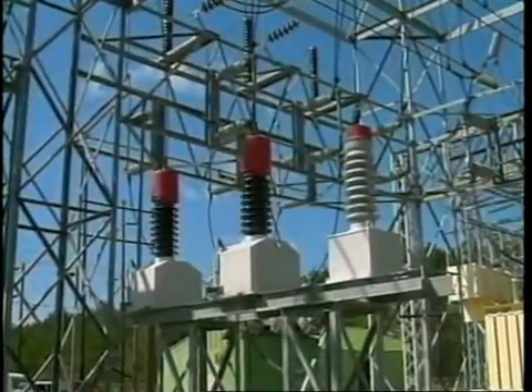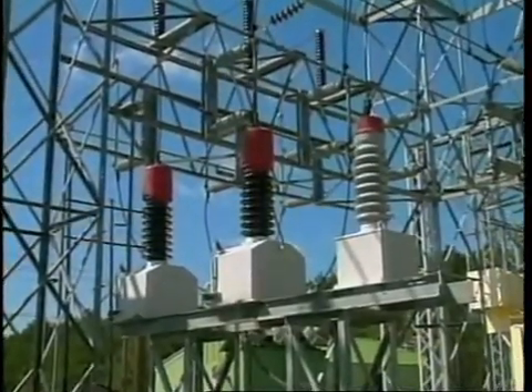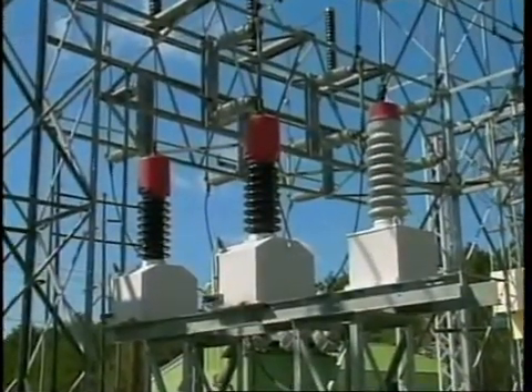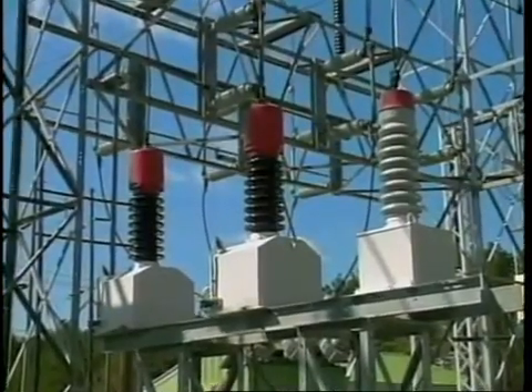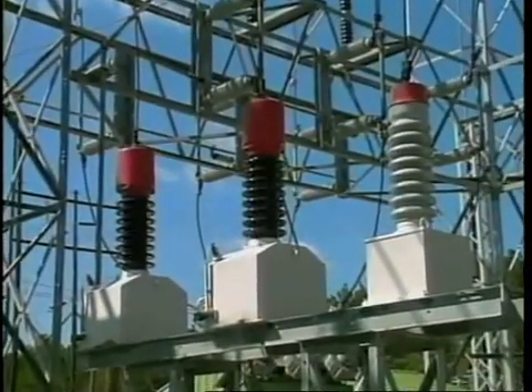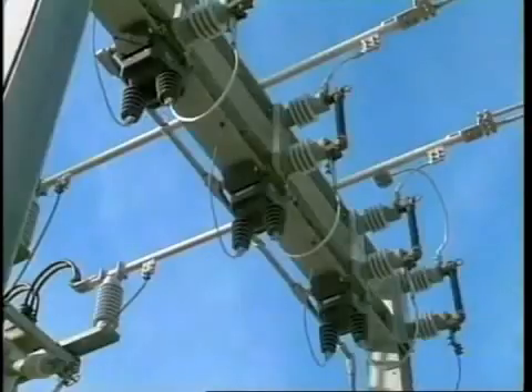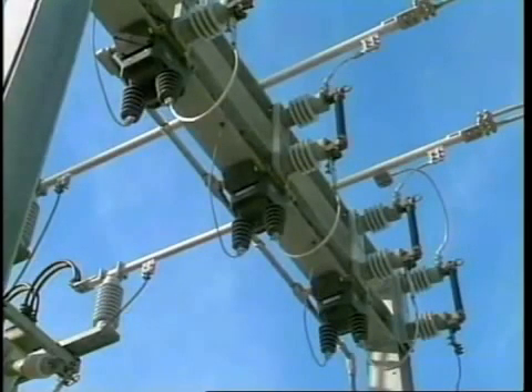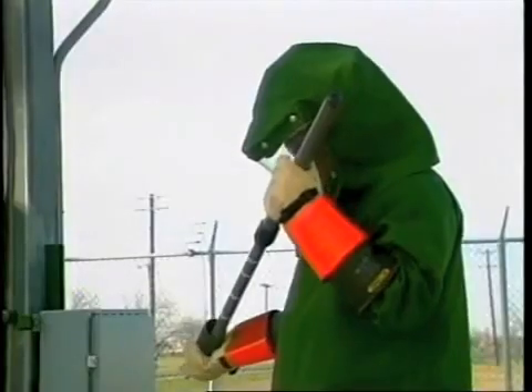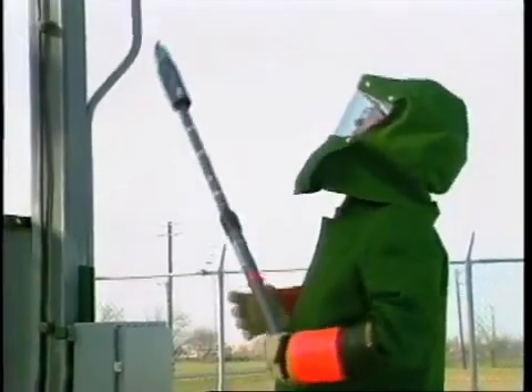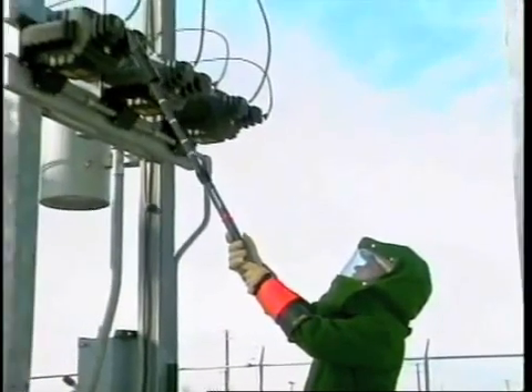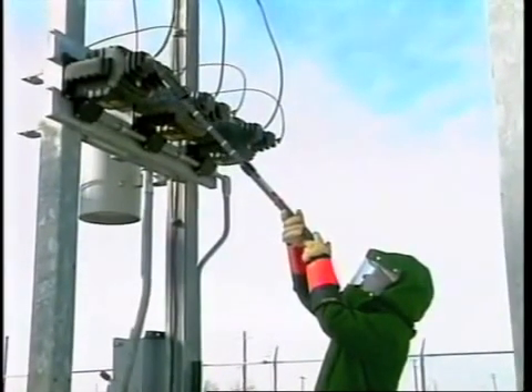potential transformers reduce high voltages to a lower voltage, usually 120 volts, for metering, protective relaying, control, and other applications. A potential transformer provides a voltage precisely proportional to the circuit it is connected to. In this program, we'll discuss generally accepted guidelines for working safely with this type of equipment.